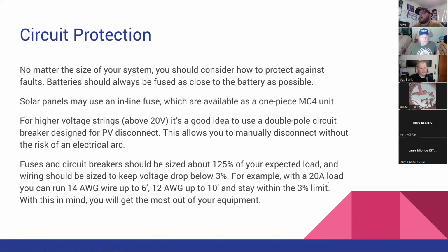For a 20 amp load up to 6 feet, you could run 14 gauge wire. Up to 10 feet, you could run 12 gauge wire. There are some pretty good charts on this you can refer to if you have questions.